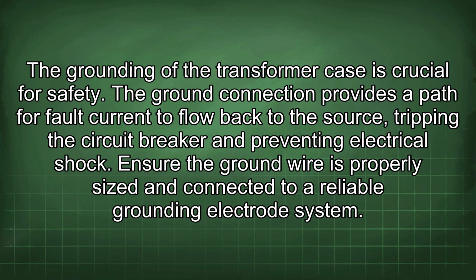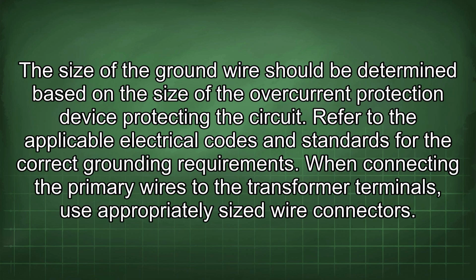The grounding of the transformer case is crucial for safety. The ground connection provides a path for fault current to flow back to the source, tripping the circuit breaker and preventing electrical shock. Ensure the ground wire is properly sized and connected to a reliable grounding electrode system. The size of the ground wire should be determined based on the size of the overcurrent protection device protecting the circuit. Refer to the applicable electrical codes and standards for the correct grounding requirements.